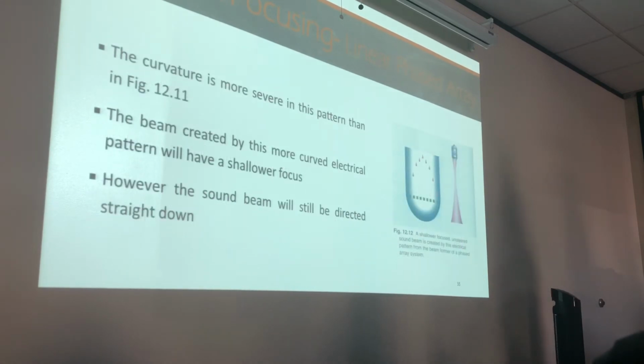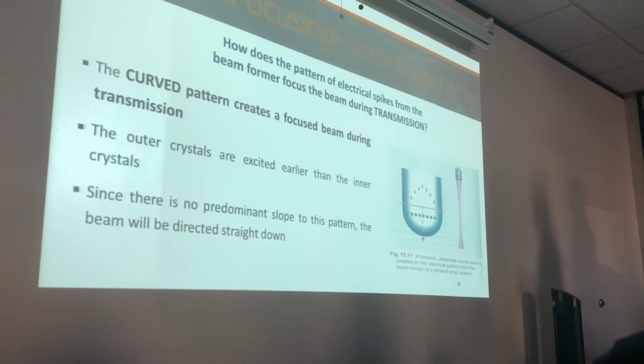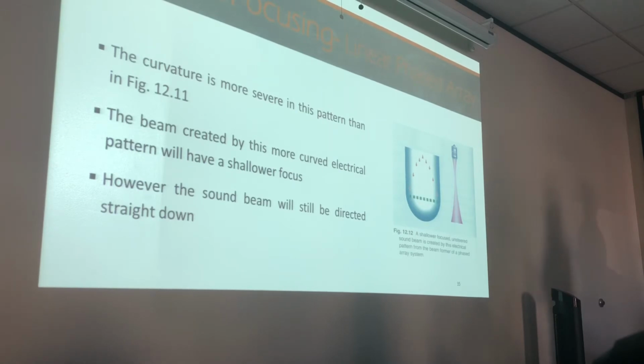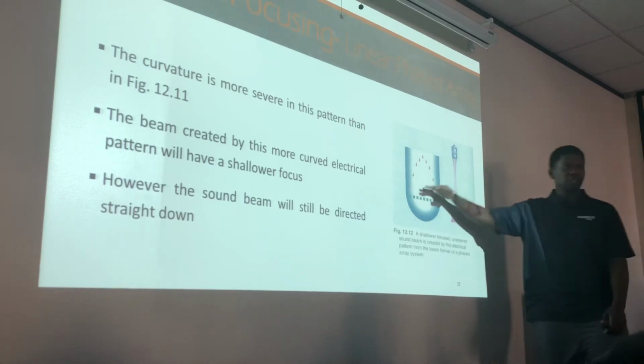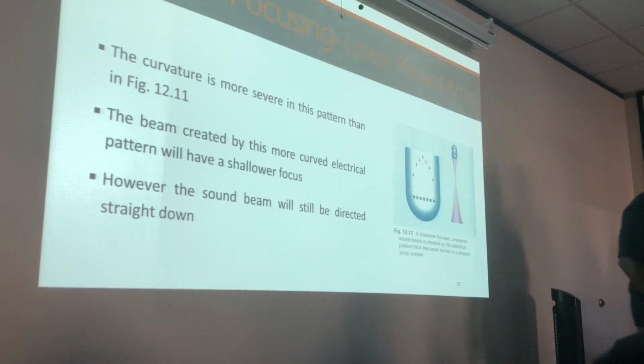Okay? So, notice right here, compare this image to this image. Notice how steep or more severe our curvature pattern is than the previous image. That's going to determine our focal depth. Okay? The beam created by this more curved electrical pattern will have a shallower focus. I would say the further away the curvature is, the shallower the focus. The closer to the active elements that the electronic signals are hitting, hitting the elements at a curvature, the deeper the focus. Okay?